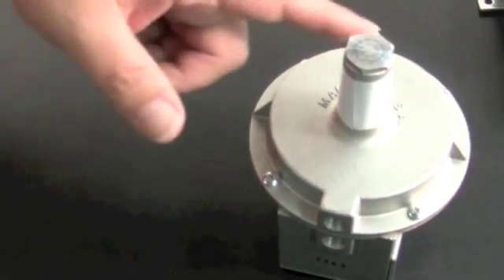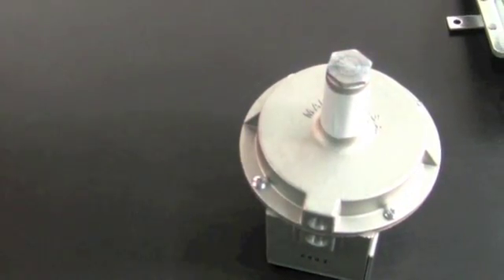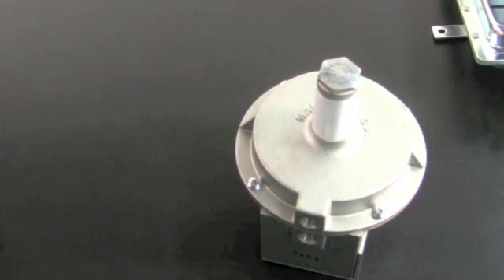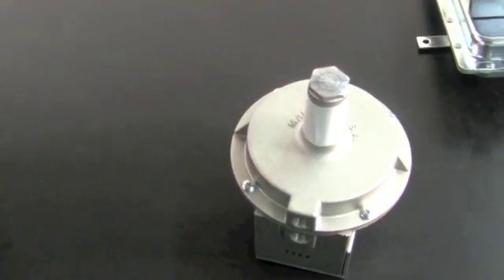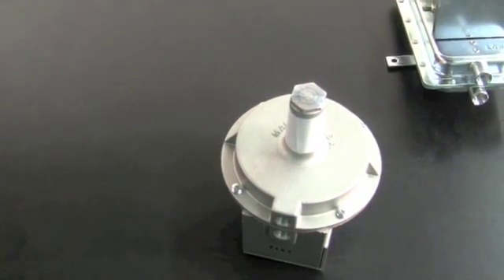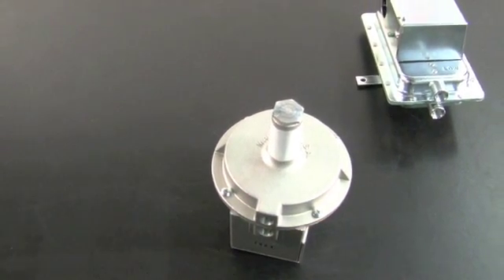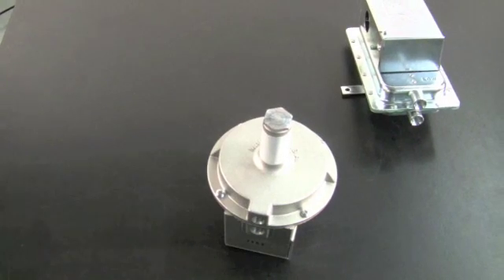Adjusting the spring is a simple matter. The spring is in here. Simply remove the nut and put a screwdriver in, and it's a simple righty tighty lefty loosey. As you advance the thread, it tightens up on the spring, raises the set point. You just want the airflow switch set so that you're making with the amount of pressure that you have on the blower.